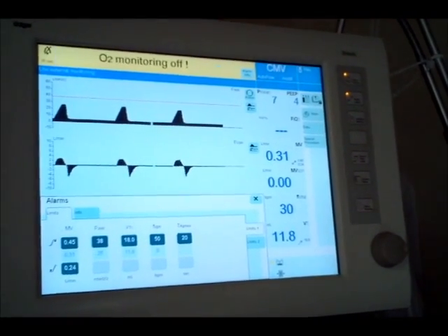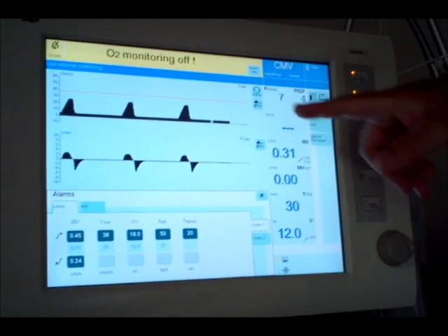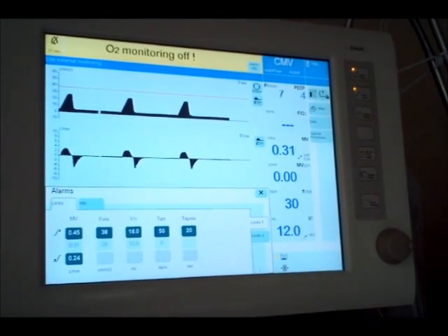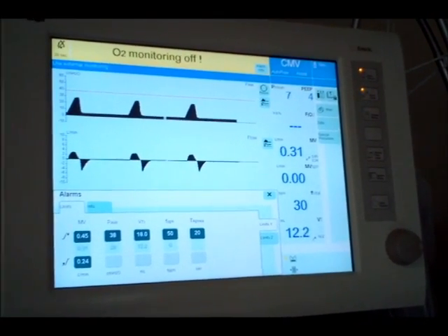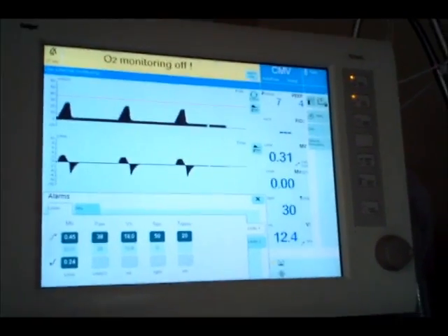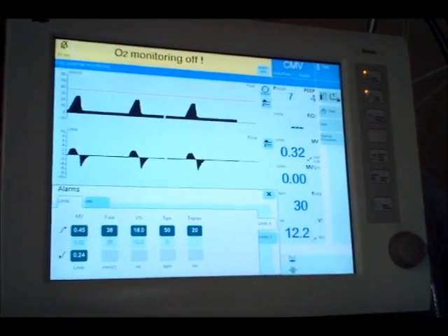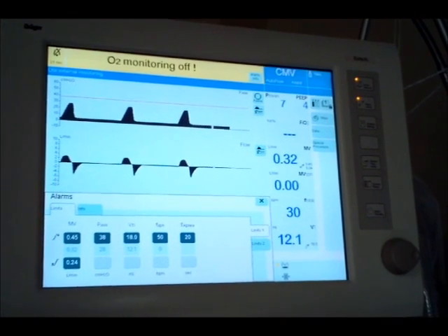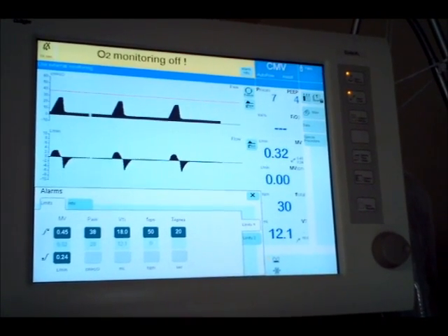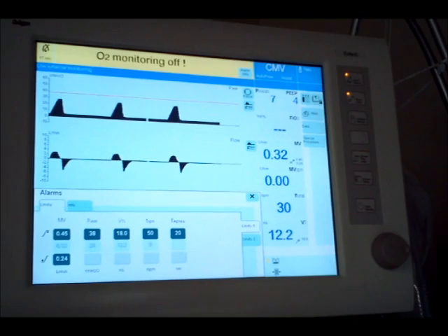Okay, so our O2 monitoring off is still on. That'll stay on, but the volume not constant alarm did go off. And now I should be getting closer to my tidal volume. And now my peak pressure is actually about 28. I picked 38. That was just a wag on where to set that. I'm probably going to leave it there.